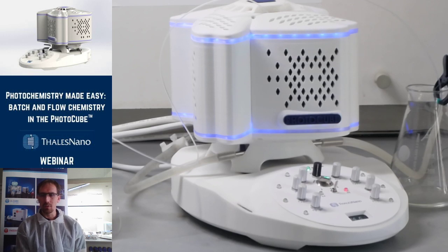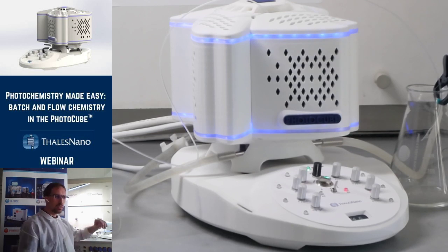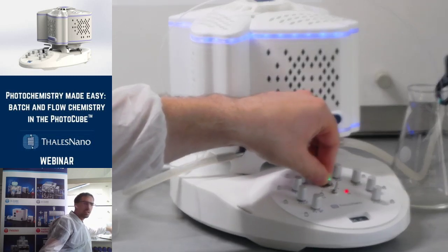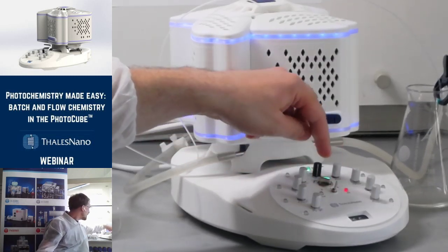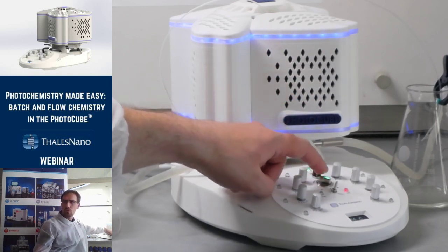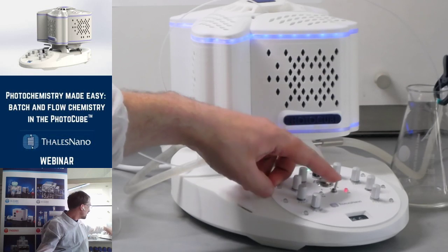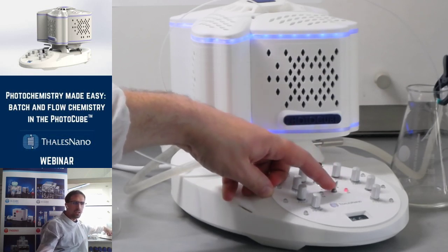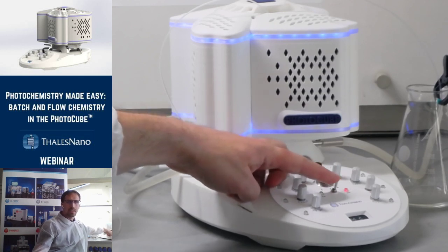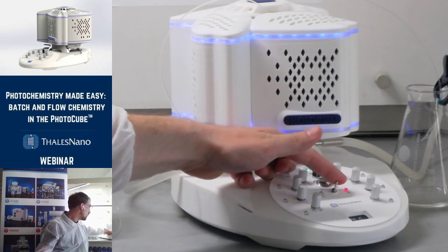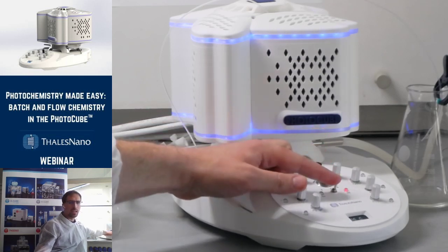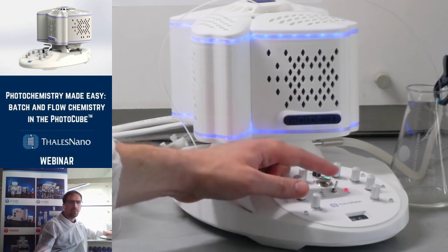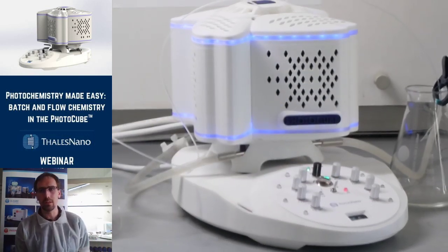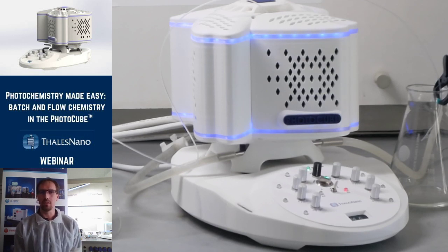What are the other two modes in the panel? So we have, can we show? Yes, we can. So we have this switch here. This can switch between 1, 2, or 4 panel irradiation. And we have this one here. We call it low and high. And this sets the current. So in high current or in high mode, you apply higher current, but you can apply high mode only if you do single color irradiation. If you go to low mode, you apply a smaller current, but you can work with multiple colors at the same time.